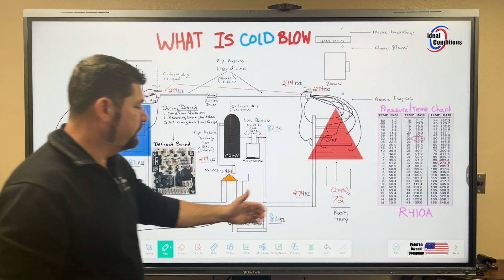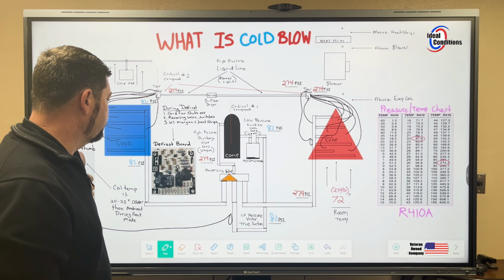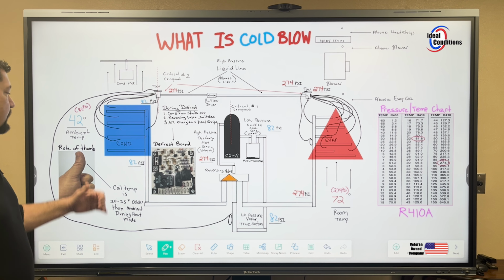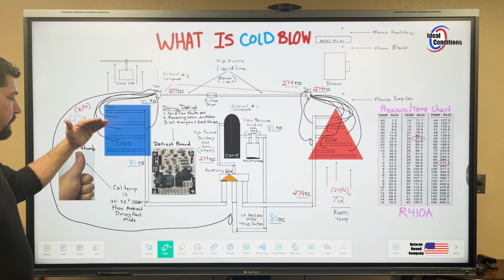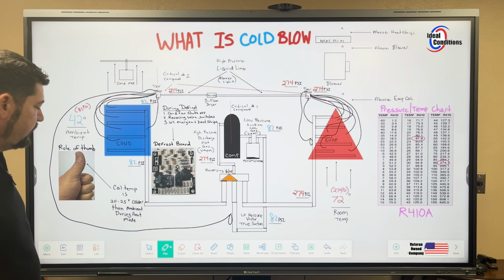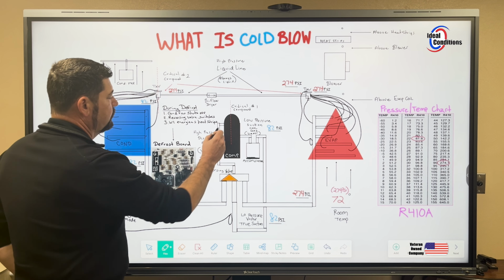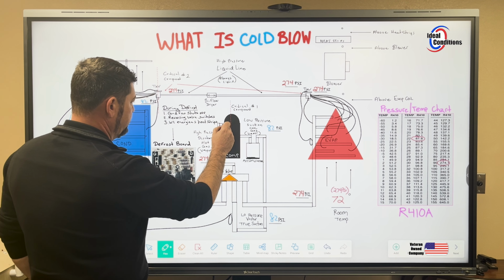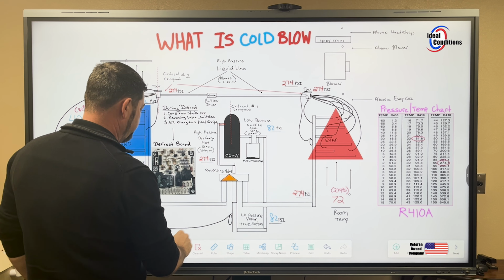And as the room temperature changes, down or up, the head pressure is going to follow down or up based on that temperature. As the outdoor temperature drops or goes up, the outside PSI for the low side is going to go up or down based on that temperature as well. This is just a good rule of thumb. And so if we wanted to look at what this would look like in color form, let me go ahead and get that mark bigger.